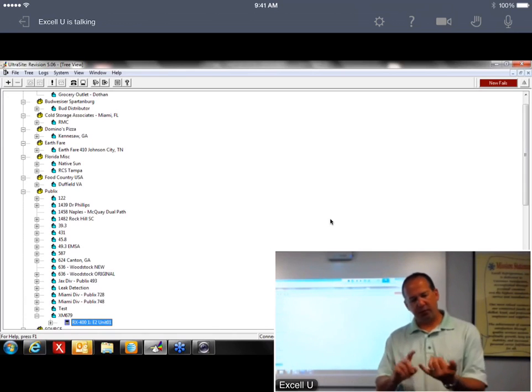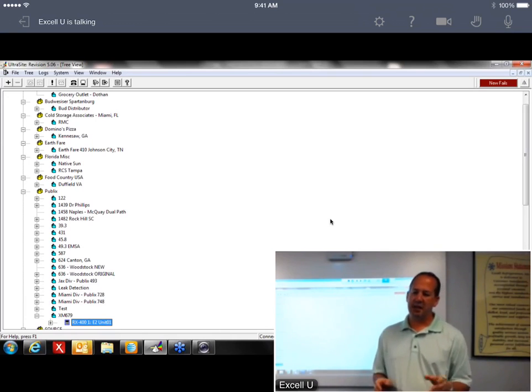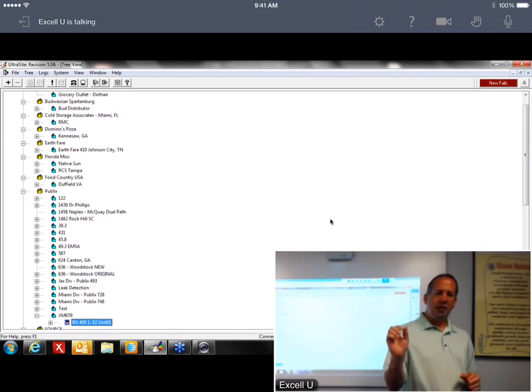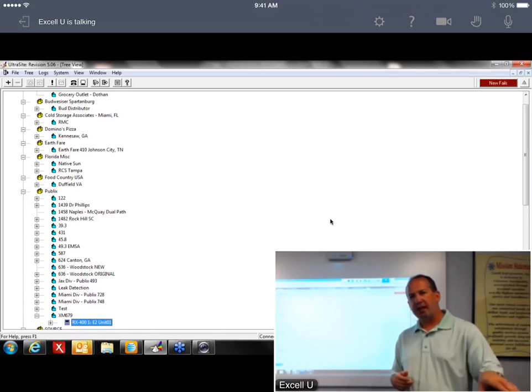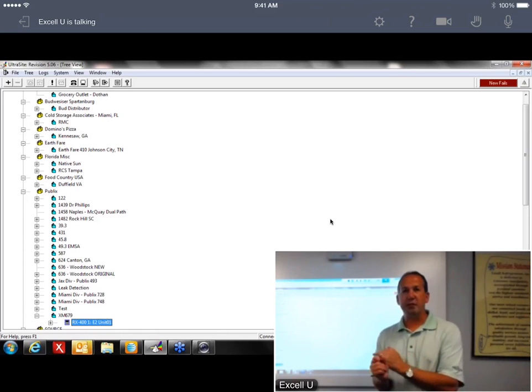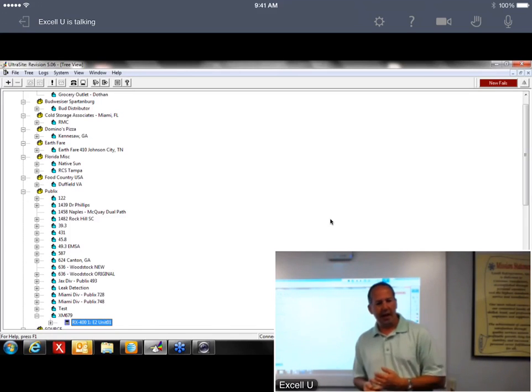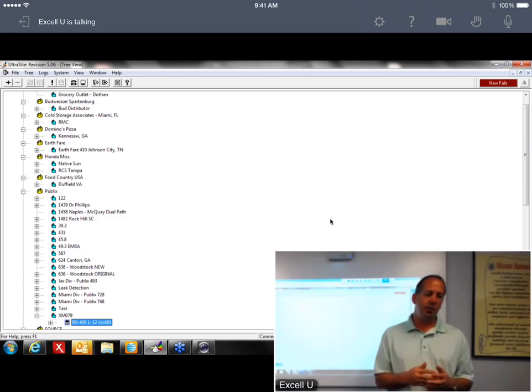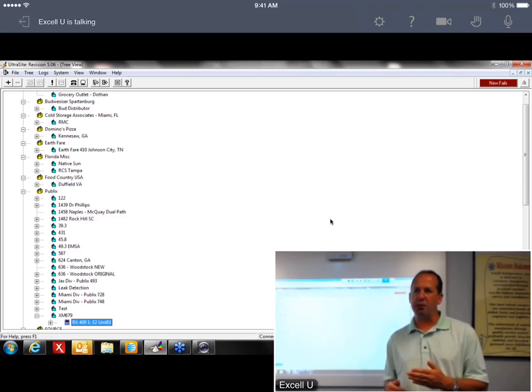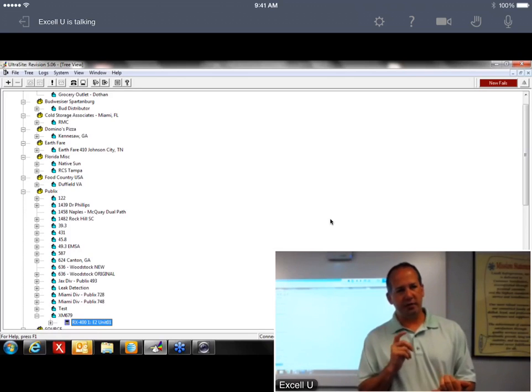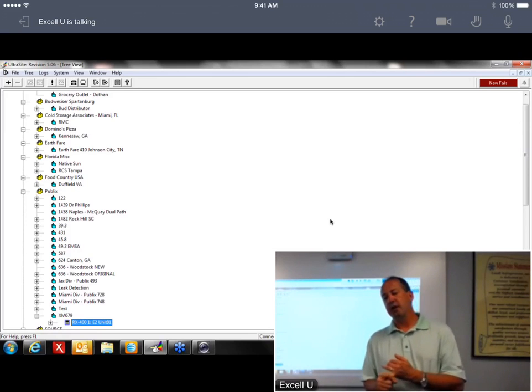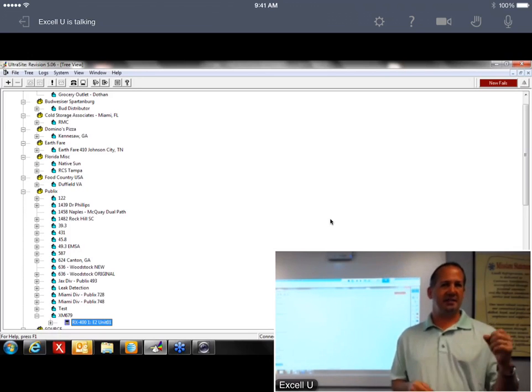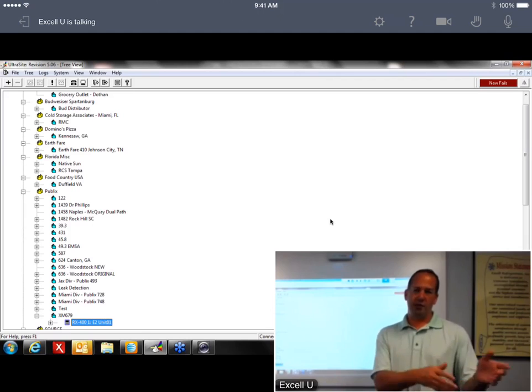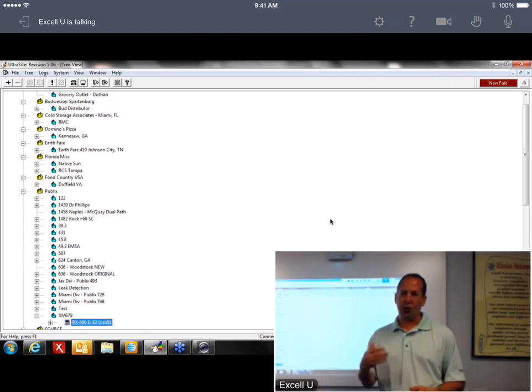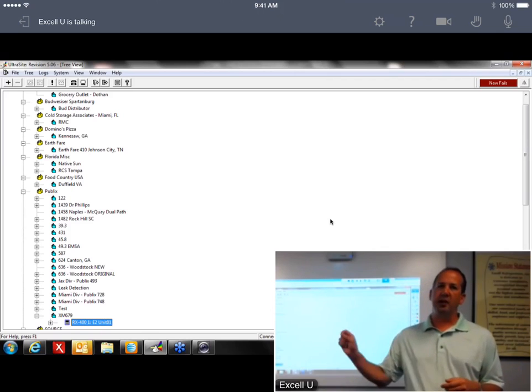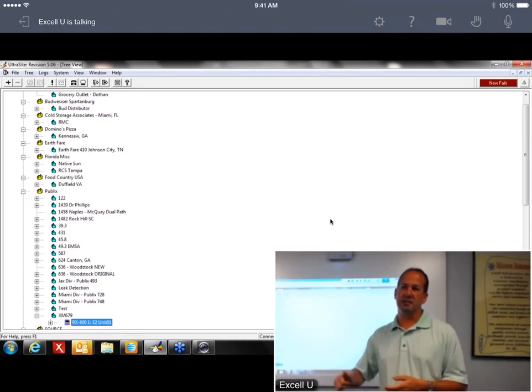One of the things too is we've got 6 sensor inputs into this thing. The E2, whenever you take the parameters out and dump them into that device, has them all set up for CPC sensors. It's going to send the parameters down for a CPC sensor on every one of those inputs. So in the case where we're not using the P3 and P4 inputs, the E2 is going to generate an alarm because it's looking for a sensor there, since we're telling it there's a CPC sensor, but nothing's connected, so it'll alarm out. We have to go in and disable those and tell the E2 there's no probe in those locations. I'll show you how to do that too.